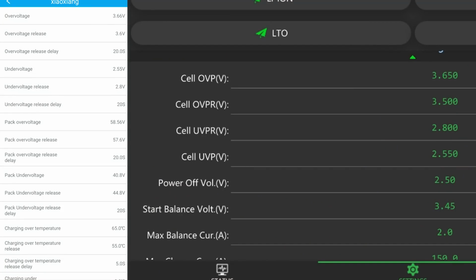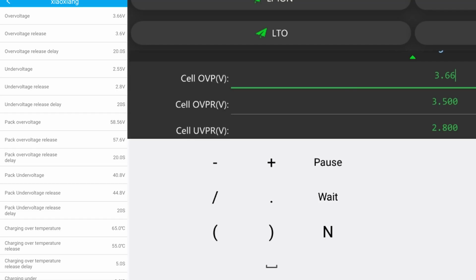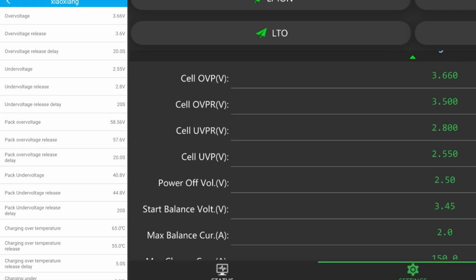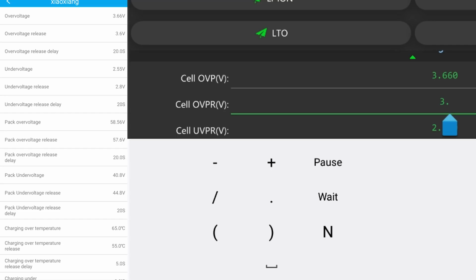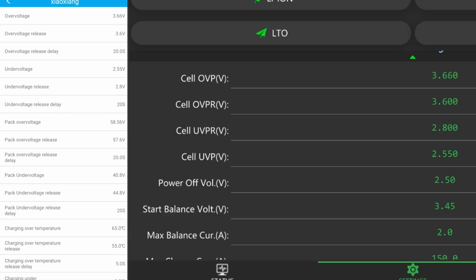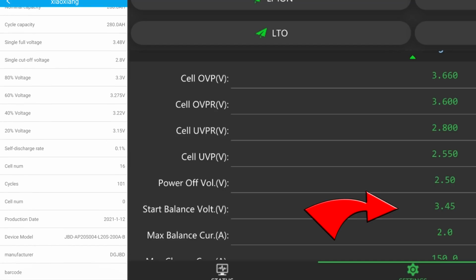Here we have the settings of both BMSs, the QUCC on the left and the JK-BMS on the right. I want to prepare everything for our high state of charge test, the high voltage test, for these two BMSs. I set the QUCC to a 3.66 volt over voltage protection, not sure if we go that high, but I set it to the same value. Then we have an over voltage release of 3.6, and I'll do the same on the JK-BMS.